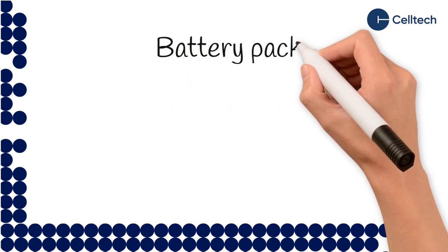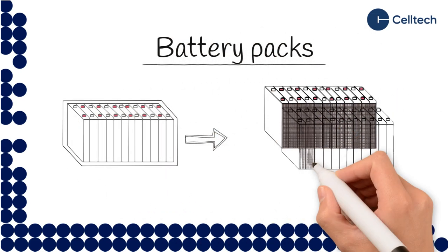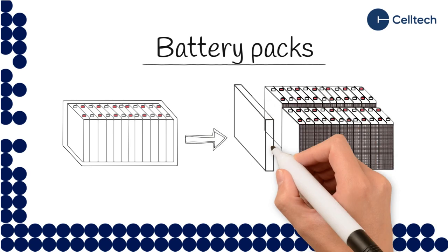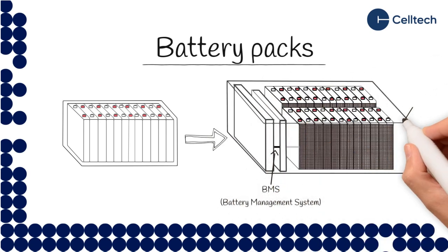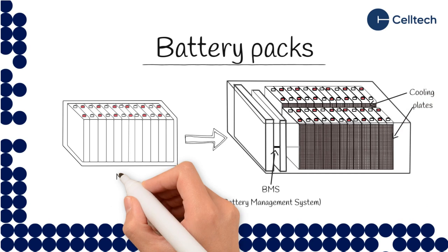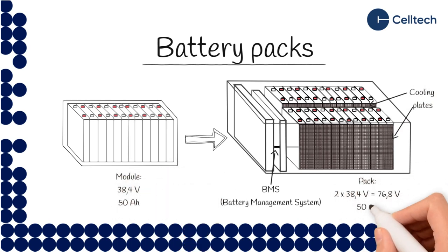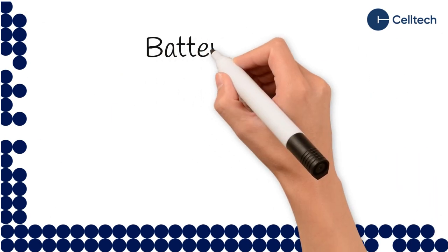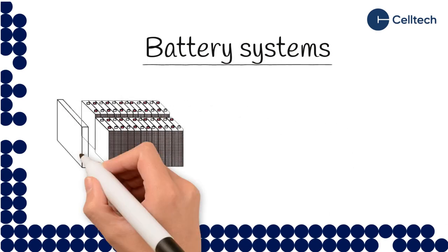When modules are put together they form a pack. A battery pack has a battery management system (BMS) that protects the battery from operating outside its safe operating area and monitors its state of charge, among other things. Inside the packs, the modules are connected in series or parallel to achieve the desired voltage and energy capacity. When packs are put together they form a system.